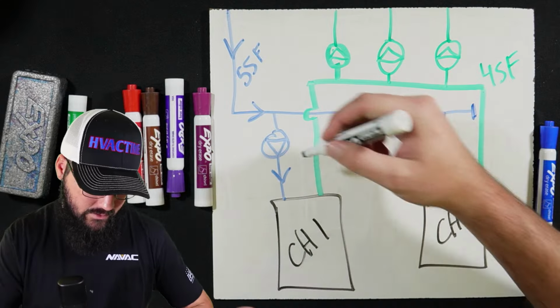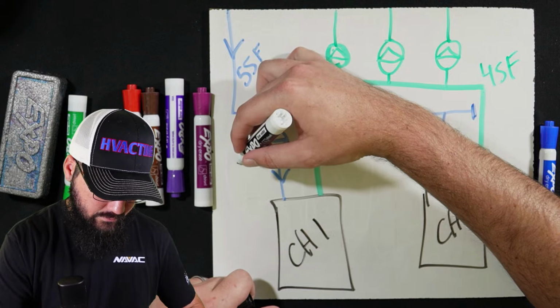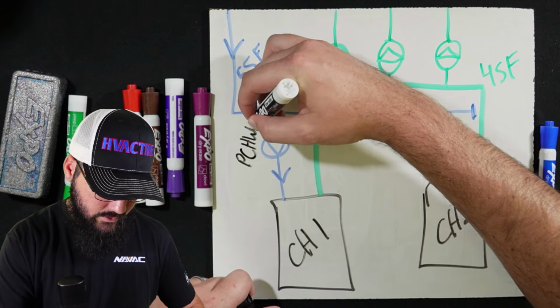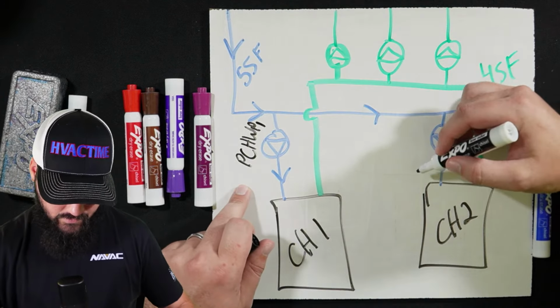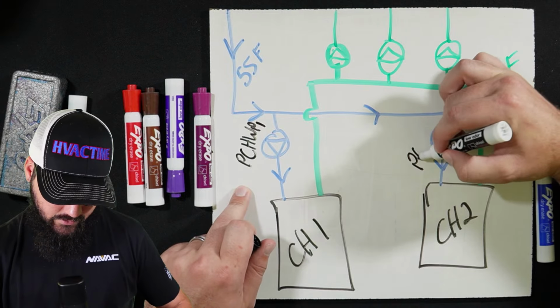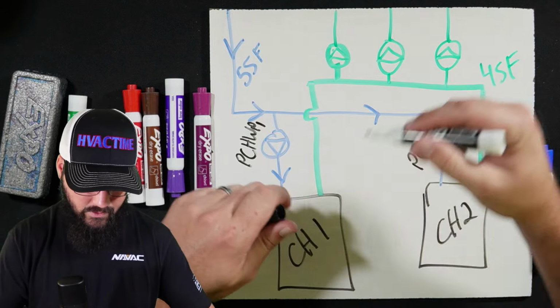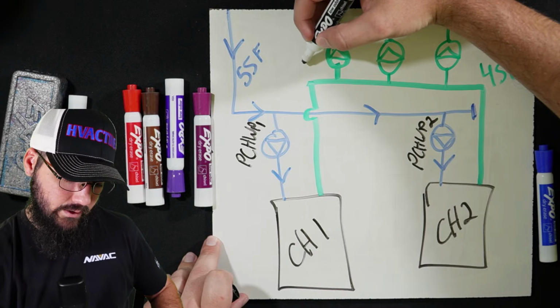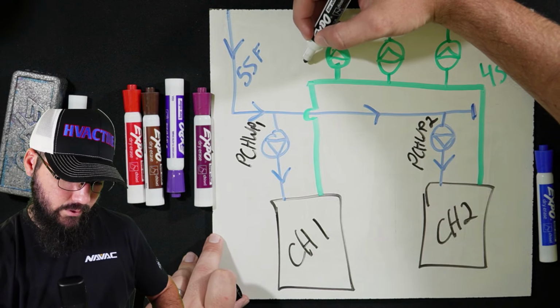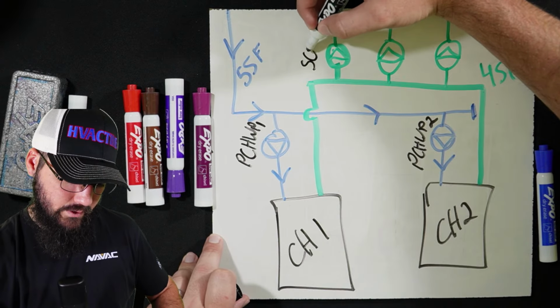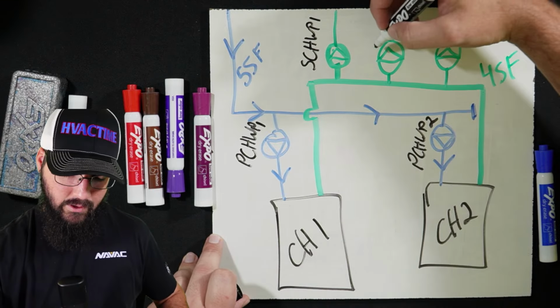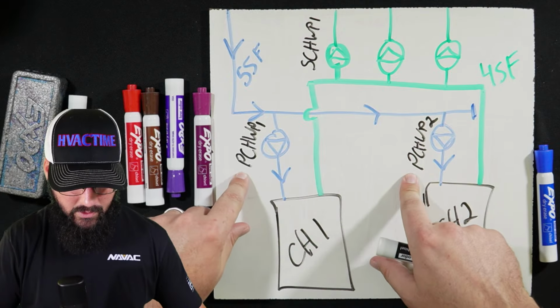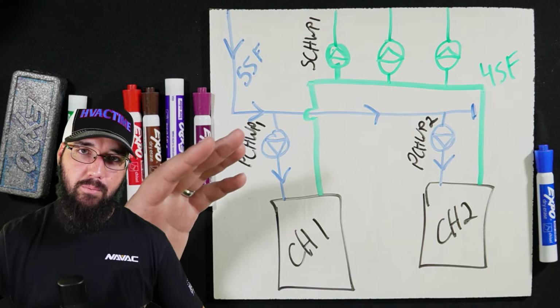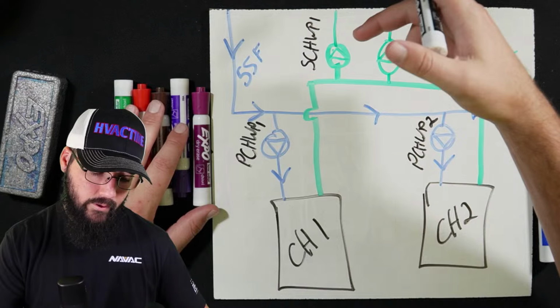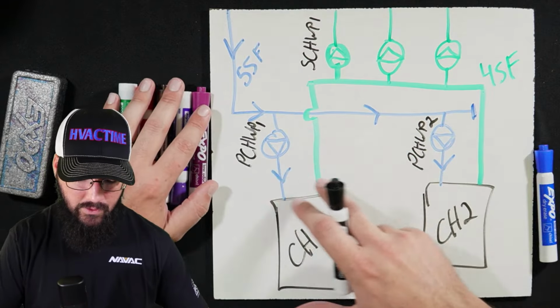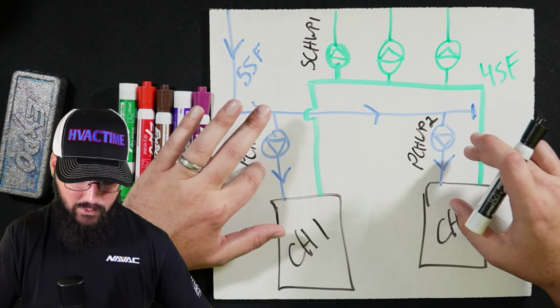They'll be identified as primary chilled water pump 1, primary chilled water pump 2. And then for the secondary, I've seen it done two ways, either S or SEC. We're going to use just S in this case. So secondary chilled water pump 1, and then pump 2, pump 3. Walking through the plant, you're seeing these labels, whether on the starter panel, say one large MCC panel, or on the actual pumps themselves. You should see some kind of labeling. It's not always done this way. I've been in plants where it was just pump 1, 2, 3, 4, 5.